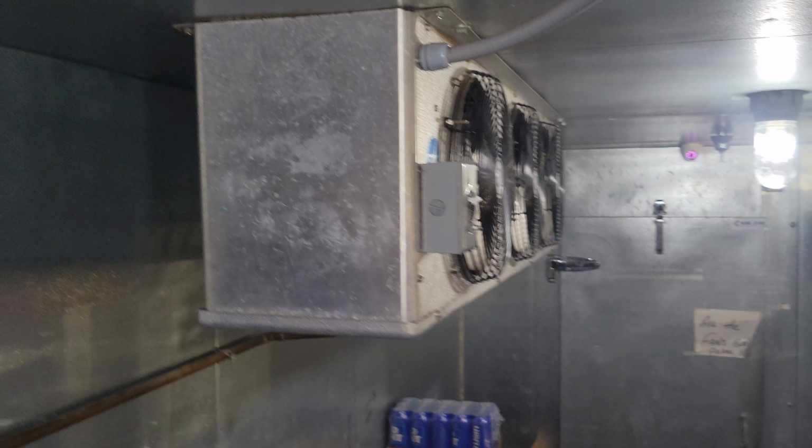So it uses the differential controller, and it says, hey, when there's a refrigeration effect across the expansion valve, break that hot leg, and then it speeds them up to 100%. And then when it doesn't sense that differential, it sends that hot leg to the motors and slows them down. So all that I did was break the comm line, the hot leg going to both motors. Therefore, they're going to run at 100%, okay? It's not great. Of course, they lose their energy efficiency, but those 2-speed motors also in certain situations can cause defrosting issues, because when the coils go into defrost, they run at low speed, which is asinine, really, because you need those fan motors running at 100% when it's in defrost, because it doesn't off-cycle defrost. It needs that air running across that evaporator at full speed to try to defrost anything.